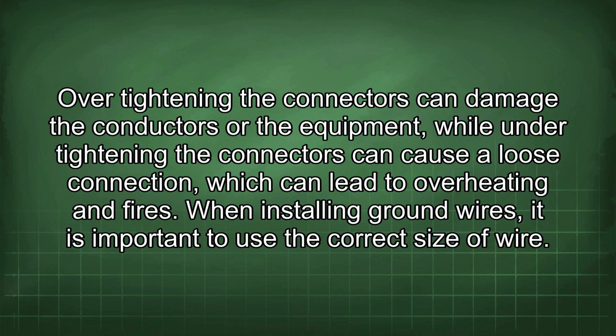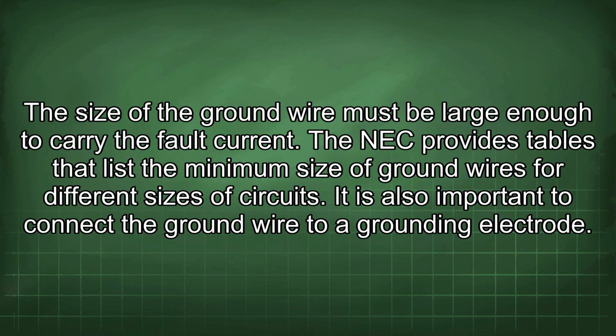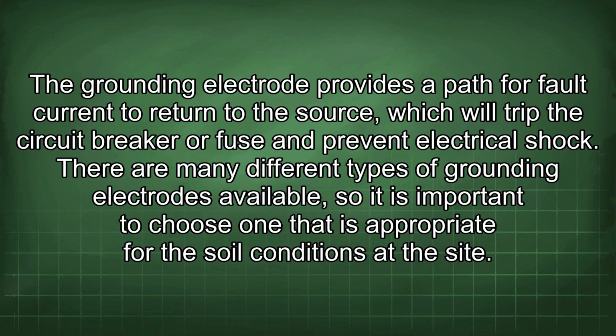When installing ground wires, it is important to use the correct size of wire. The size of the ground wire must be large enough to carry the fault current. The NEC provides tables that list the minimum size of ground wires for different sizes of circuits. It is also important to connect the ground wire to a grounding electrode. The grounding electrode provides a path for fault current to return to the source, which will trip the circuit breaker or fuse and prevent electrical shock. There are many different types of grounding electrodes available, so it is important to choose one that is appropriate for the soil conditions at the site.